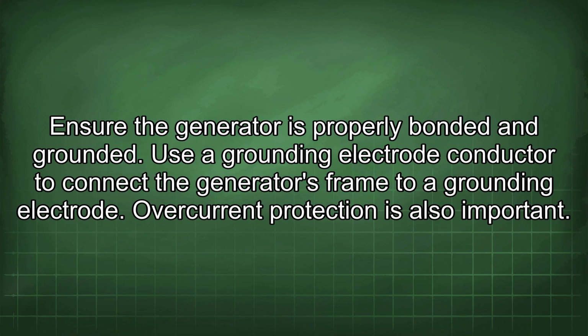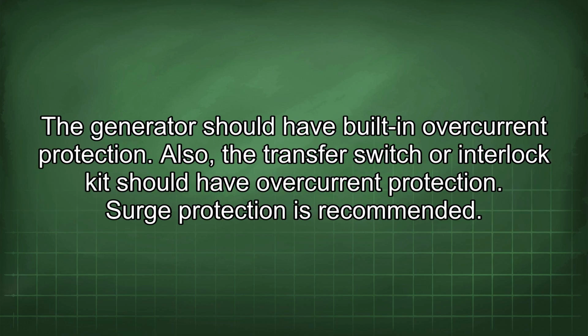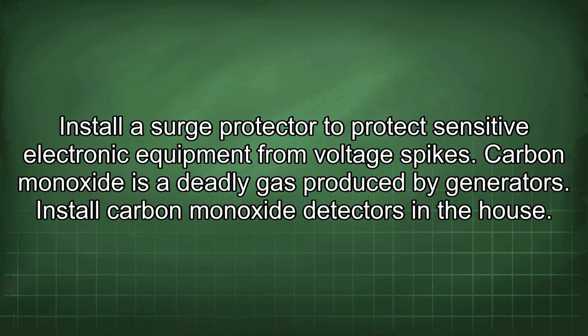Overcurrent protection is also important. The generator should have built-in overcurrent protection. Also, the transfer switch or interlock kit should have overcurrent protection. Surge protection is recommended. Install a surge protector to protect sensitive electronic equipment from voltage spikes.